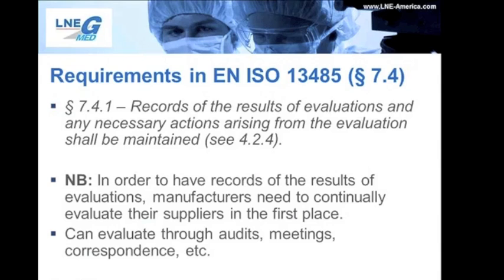So going back to section 7.4.1, it states that the records of the results of evaluations and any necessary actions arising from the evaluation shall be maintained. So basically, this means that a manufacturer must maintain the records of the evaluations they performed while choosing and then controlling their critical subcontractor. Now, on this slide, there's a note, which we'll revisit in a lot more detail later on when we talk about the recommendation. But since it ties in here, it's well worth talking about.